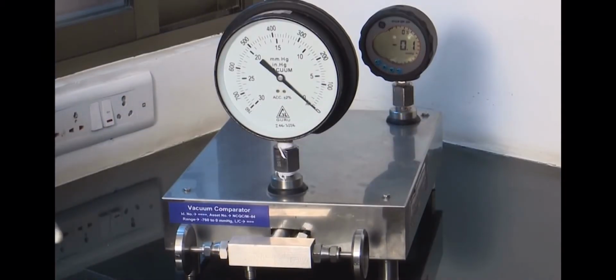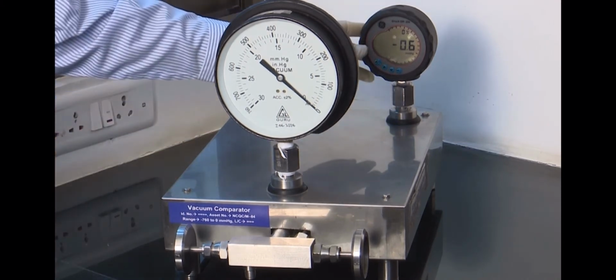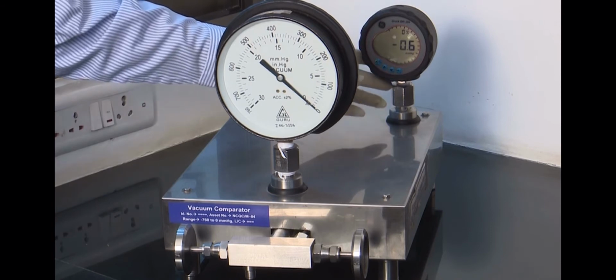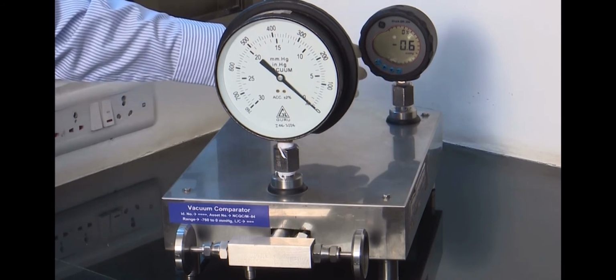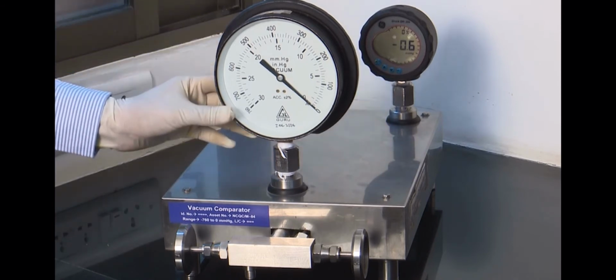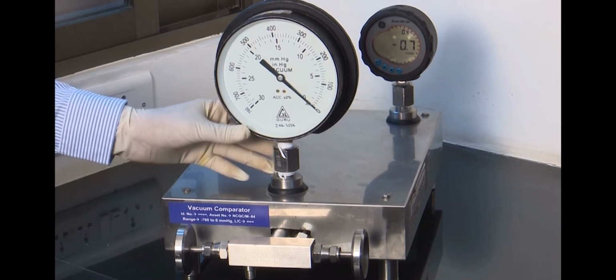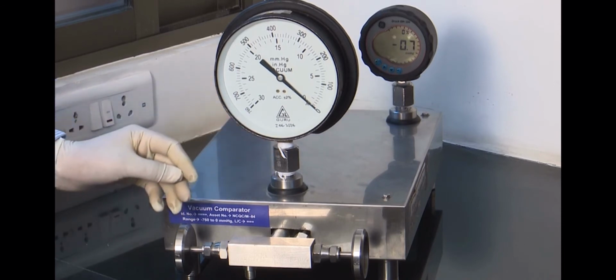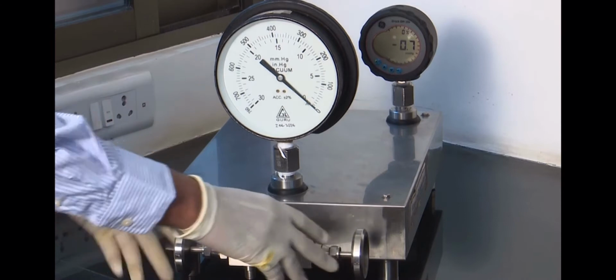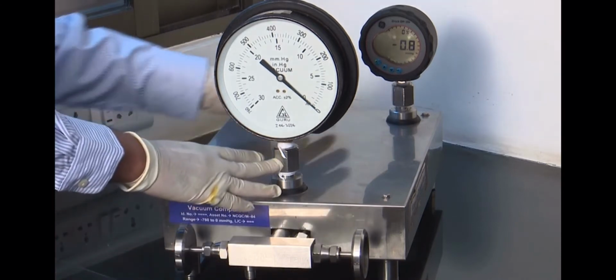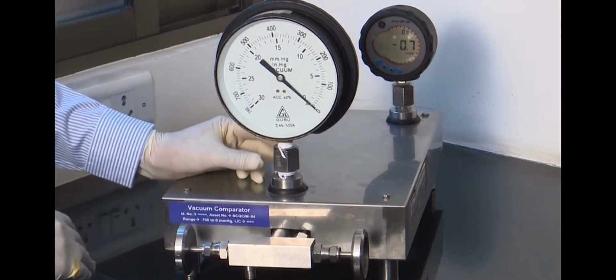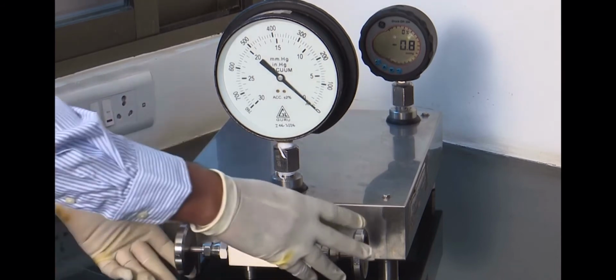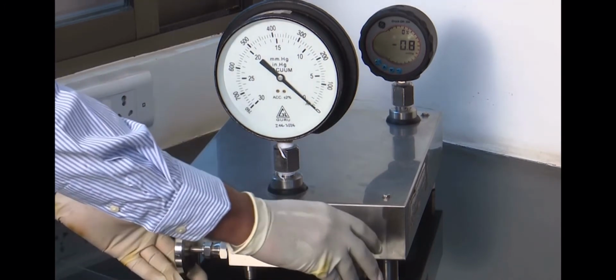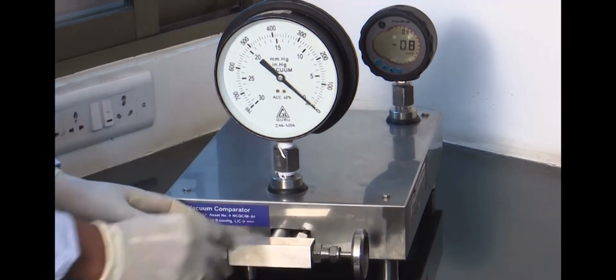For calibration, we need to do some preparations. For this, I have already mounted reference gauge on the backside of the comparator and the vacuum gauge, that is UUC, has been mounted at front side of vacuum comparator. Ensure that both the gauges are tightened properly on the vacuum comparator. Ensure that isolation valve and regulating valve of vacuum comparator are closed.